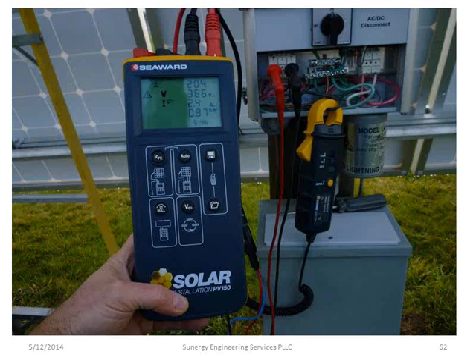And then I look at what the manufacturer specifications are, plus or minus 3%, and that's what I expect it to be at. And you can take into account, if you're doing multiple tests annually, what the degradation of the module should be to meet the warranty. You can take that all into account too when you do that. But the nice thing is you can put it in a spreadsheet and you can do this fairly automatically.